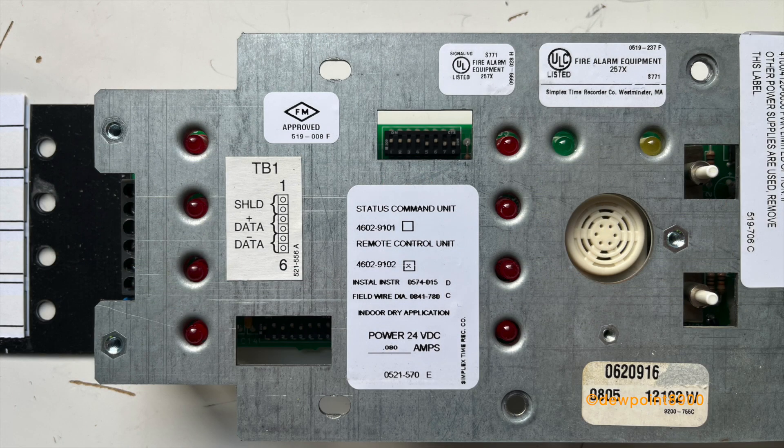Each annunciator has two sets of dip switches. One sets the serial address, while the other sets the kind of panel it's connected to. For the 4002, the LED mapping of each point is also set with these dip switches. The SCU and RCU will be updated to operate on the 4005, 4020, 4100 series, later 2120s, and ES series panels.